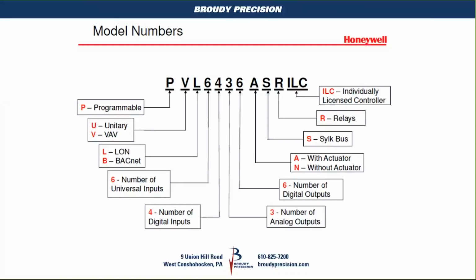Now, the VAV types come in two flavors as well, with actuator and without actuator. Your non-actuated VAV controller will have an N there, and the actuated will have an A. They all are Sylk. Every single Spyder that is manufactured comes with a Sylk bus. It's a Honeywell proprietary communicating bus. Again, it's not polarity sensitive. And one of the reasons I stress the level 4 communication cable is that we can use that for the Sylk bus as well.